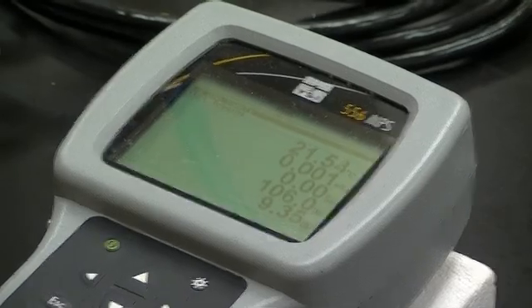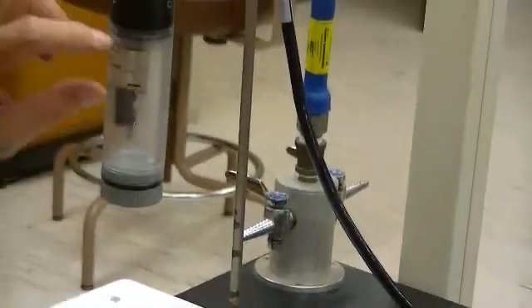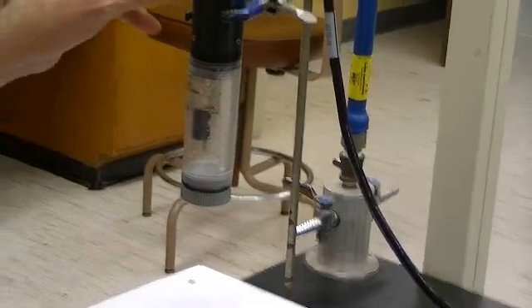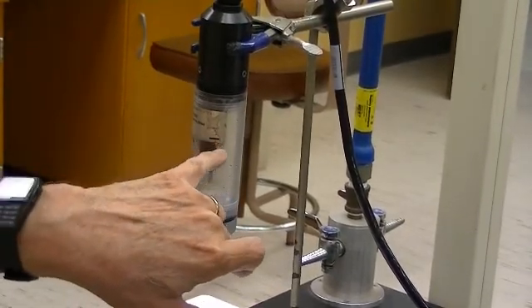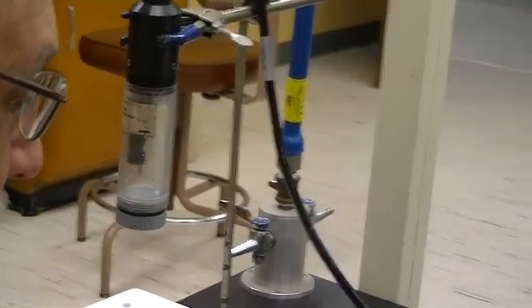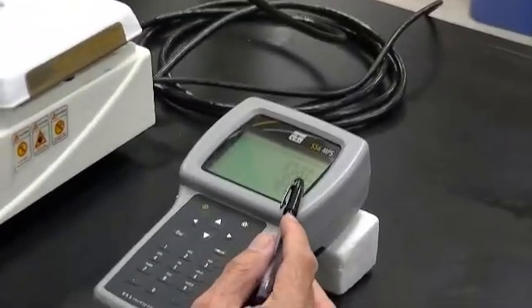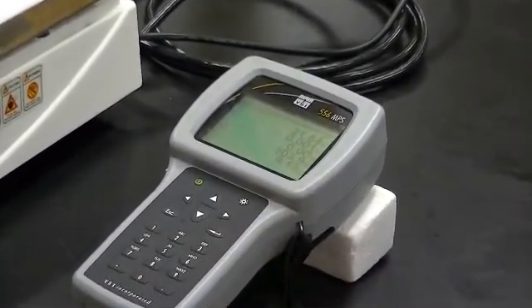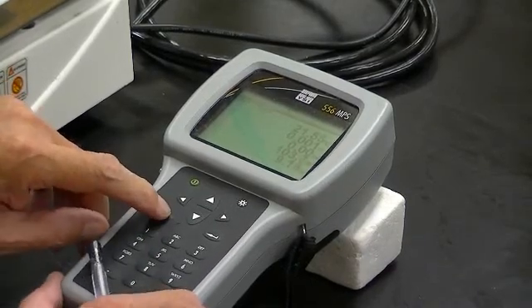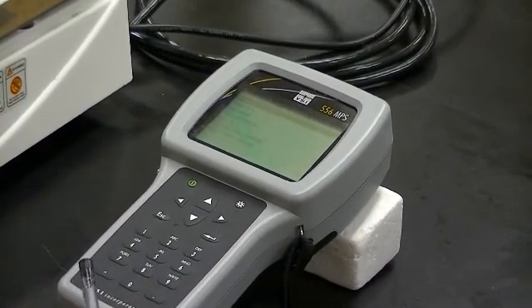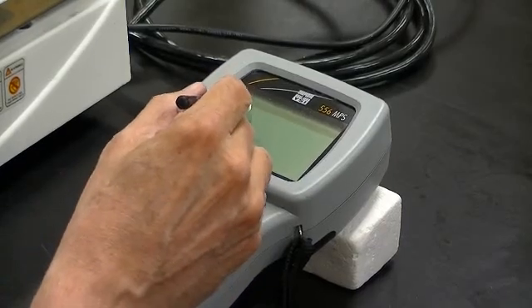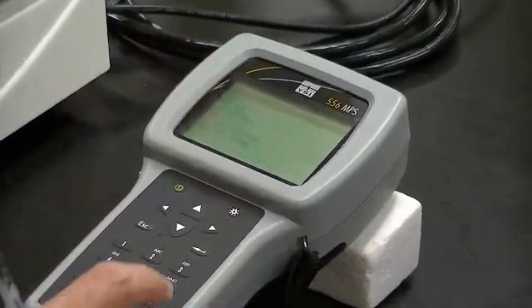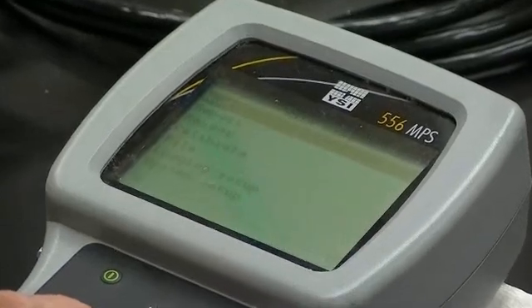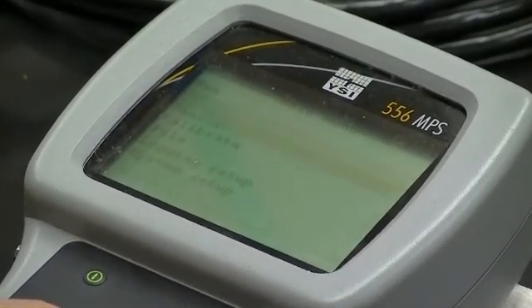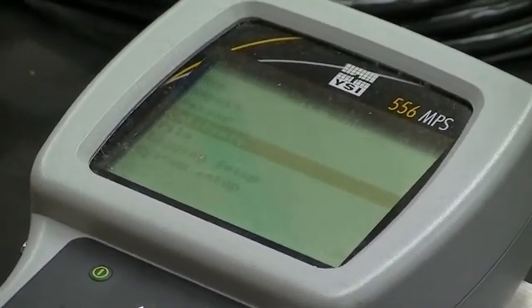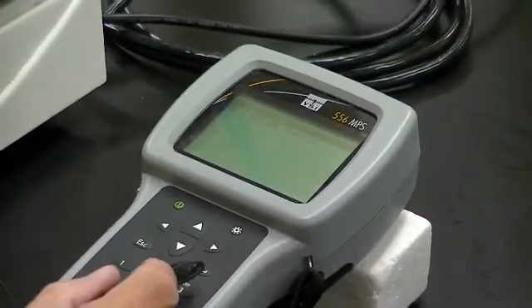Now the sensor for the oxygen is the yellow probe that's up here that you can hardly see behind that label, but you've seen it when you did the salinity lab. Okay, so now this is settling down a little bit. So now we do the calibration. You press escape, and that gives you the main menu, and the fourth item down is calibrate. So you go with the down arrow, 1, 2, 3, 4, calibrate, hit the return key.